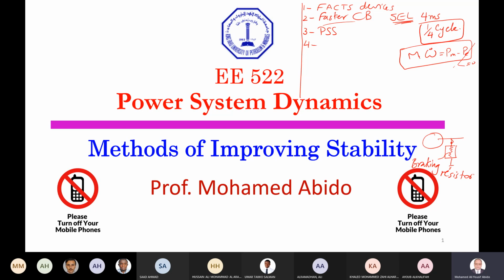Of course, this is a resistance. For example, the size of this resistance is 100 megawatt. It is not just a small resistance. You can have 140 megawatt even in real life. A resistance that can dissipate 140 megawatt. So this is a resistance that can be inserted into the system to increase the electrical power. So we can reduce this. So one of the ways to improve the stability is a braking resistor if we have a fault.